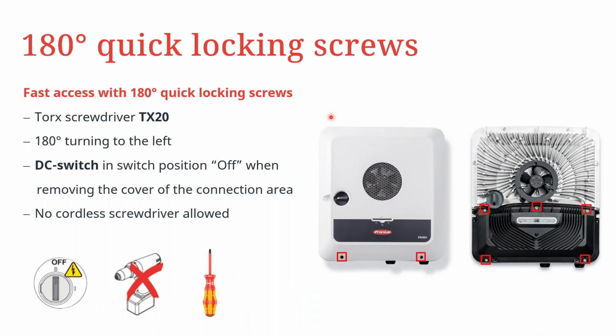So let's now talk about the wiring of the GEN24 Plus inverters. The other special attribute of the GEN24 Plus inverters is the fact that these inverters come with 180 degrees quick locking screws, and therefore this means that to tighten or to unscrew the screws from the inverter, you do not need to go the full motion like we are used to with the Snap inverters. This is only done by making a 180 degrees turn to the left or to the right, depending on whether you want to tighten or loosen the screw.